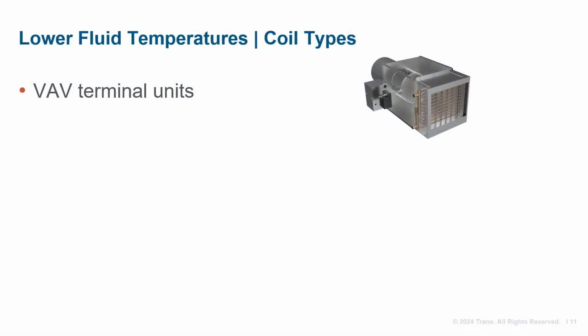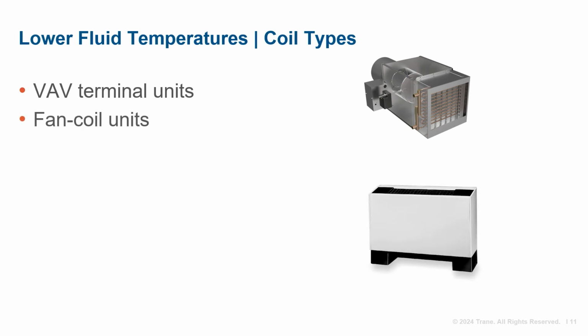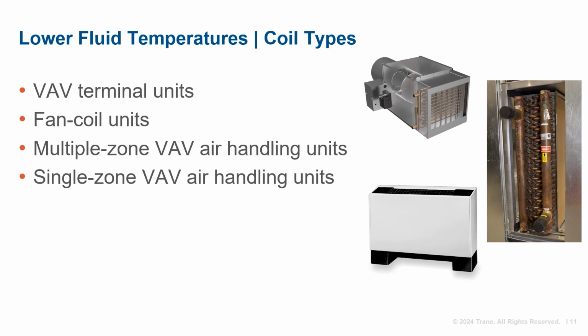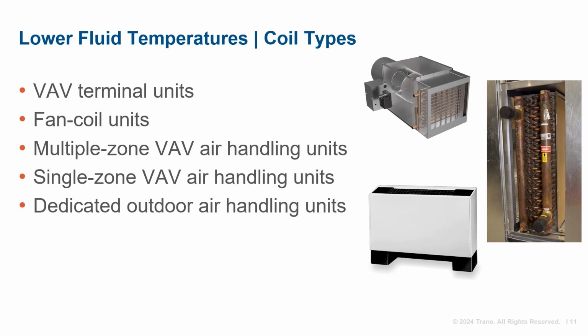In an effort to retrofit existing buildings, there may be zone or system level equipment in play. To name a few, at the zone level, VAV boxes with reheat coils, fan coils, either changeover or 4-pipe units, may be in place. When it comes to air handling units, single or multiple zone VAV air handler unit coils are likely to require consideration, along with dedicated outdoor air units designed to condition 100% outdoor air that may have been receiving much warmer water in the past.